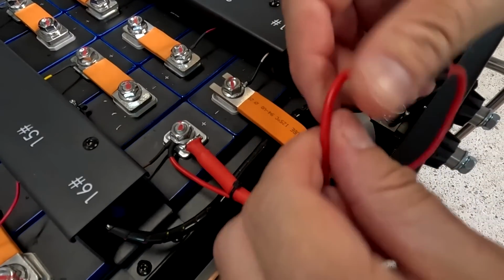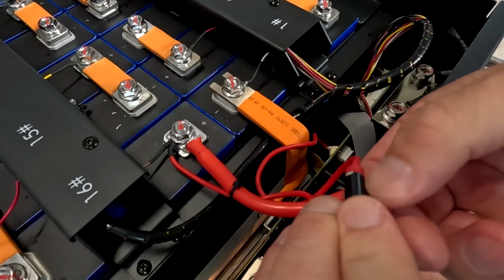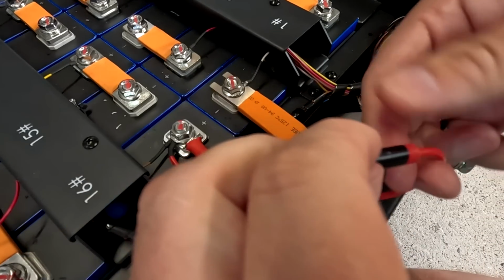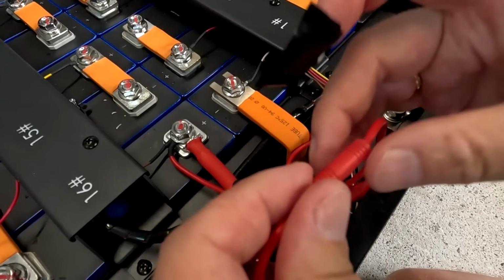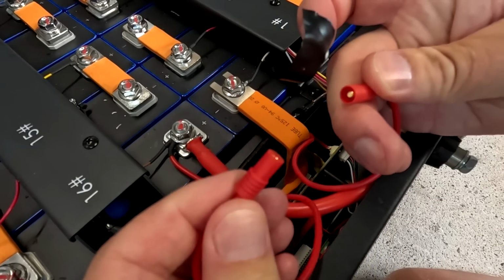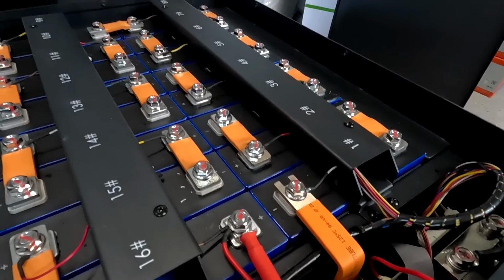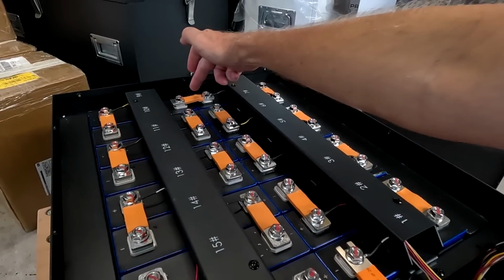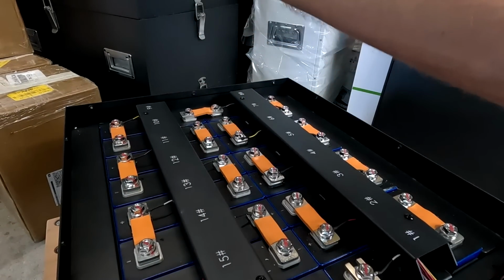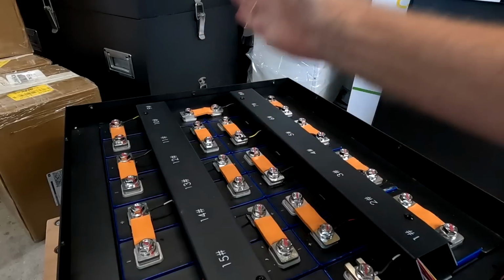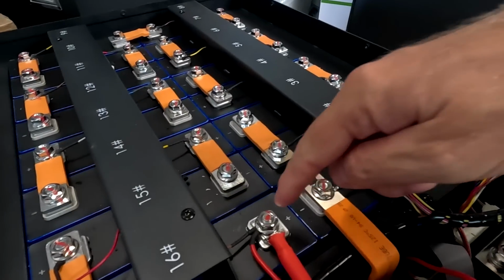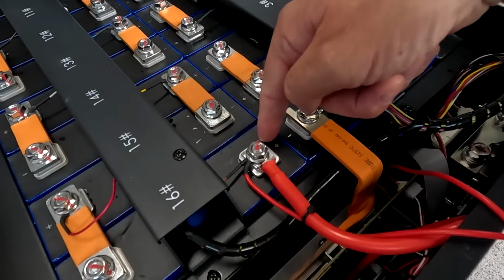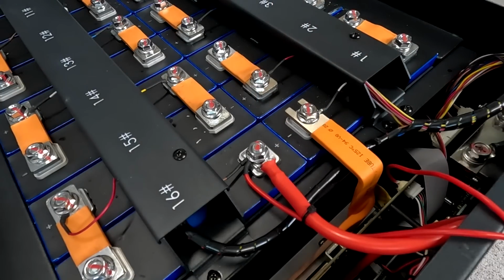And we should have - yep, here it is. Oh, this comes with some electrical tape around it so it doesn't disconnect accidentally. We turn off the positive to the BMS, and usually what I also do is disconnect this bridge here. This basically splits the battery in half, 24 volt, and takes away the 48 volt here at the main positive and negative of the battery, just in case something happens - you don't have the 48 volt on these two terminals anymore.